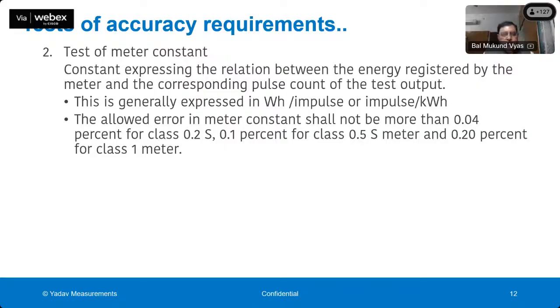Another is the test of meter constant. As I told you, the constant expresses the relation between the energy registered by the meter and the corresponding pulse output. The unit is watt hour per impulse or impulse per kWh, whatever is there. The accuracy of this meter constant has to be tested by passing a specified load through the meter and counting the number of pulses the meter has given, and verifying whether this relationship is accurate or not.